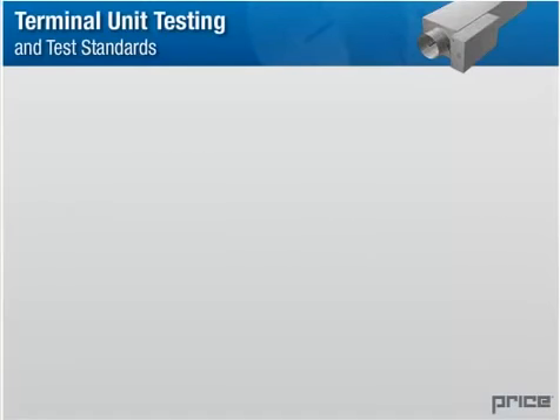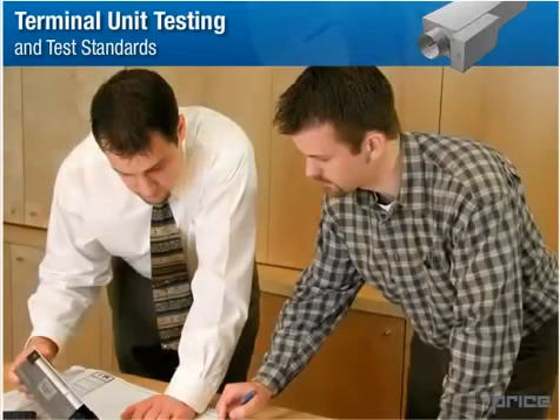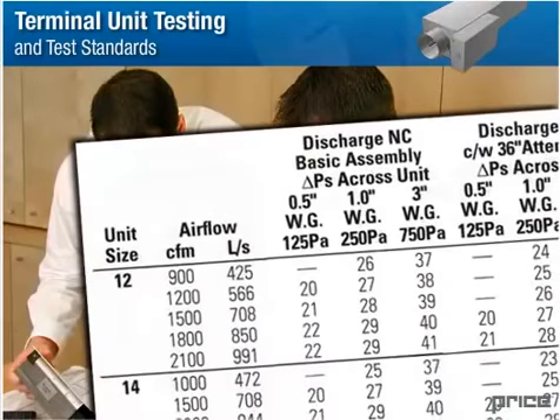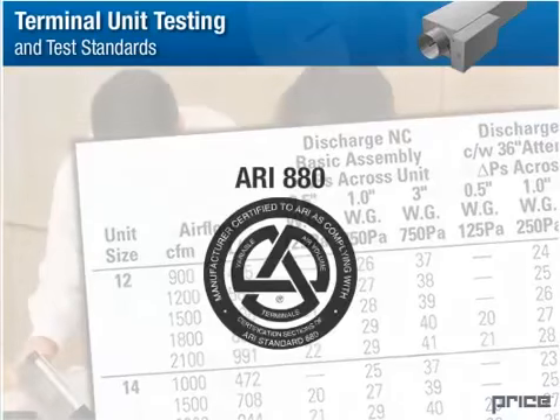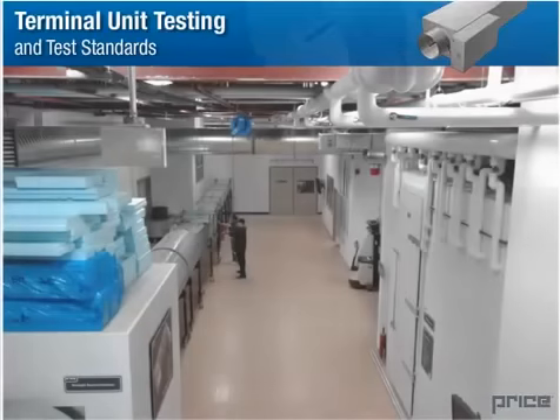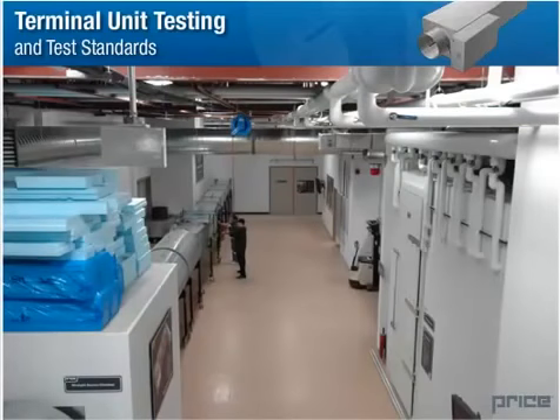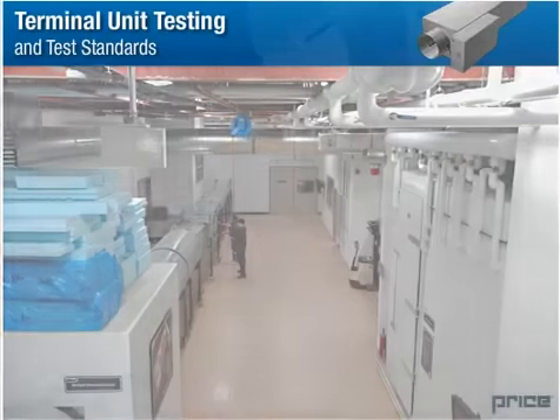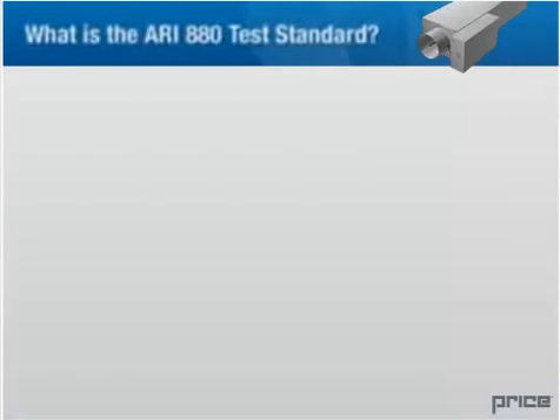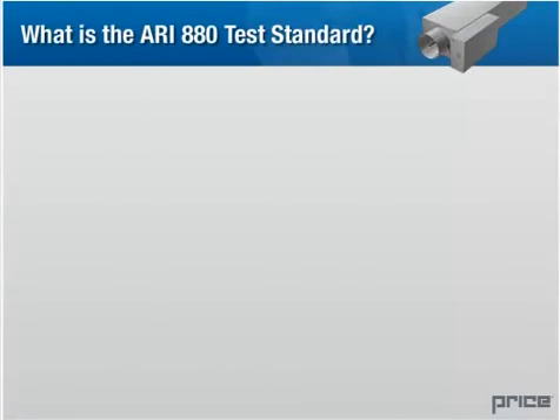Terminal unit testing and test standards. An integral part of the HVAC designer's job is to be able to predict sound levels of terminal units and produce an NC rating acceptable to the project goals. Predictions are often made using data acquired in accordance with the ARI 880 test standard. The ARI 880 test standard allows the manufacturer to gather accurate test data for both discharge and radiated sound levels for a given unit. What is the ARI 880 test standard?